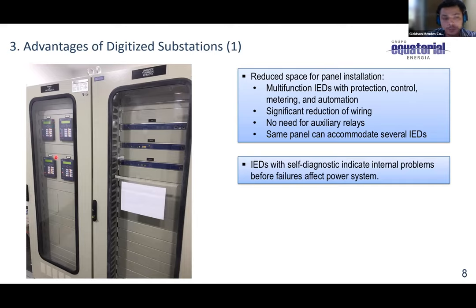So in this specific substation, we have four relays, and we have four more slots for more relays if you want to expand the substation. So we have a reduction in equipment, a reduction in space, and a reduction in the use of wiring, as Ricard said in his presentation. We don't need auxiliary relays for monitoring specific points anymore, because the digital relay can do all these tasks by itself. In the same panel, it accommodates many different relays.